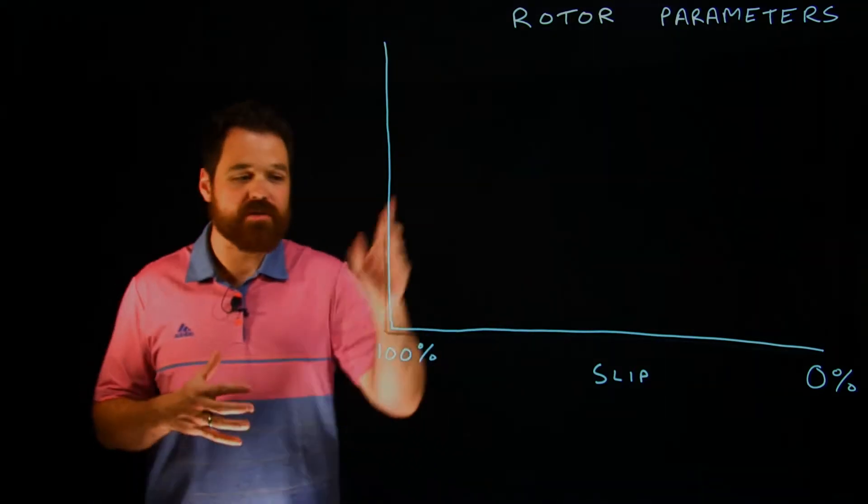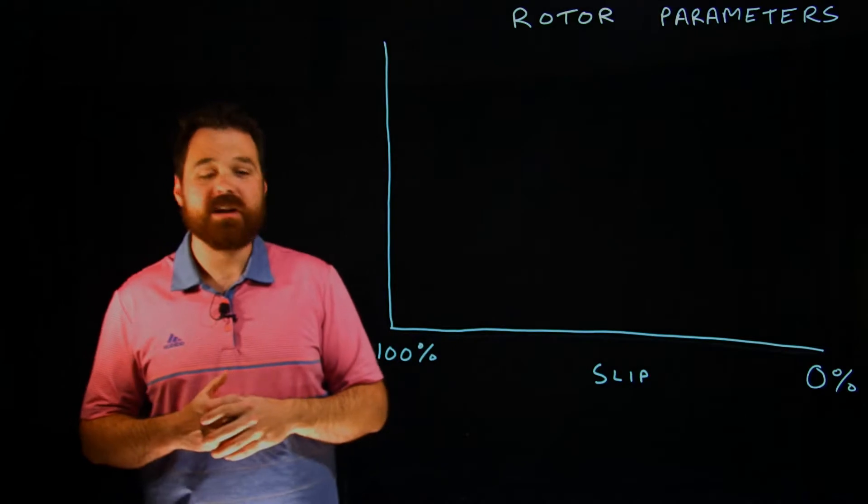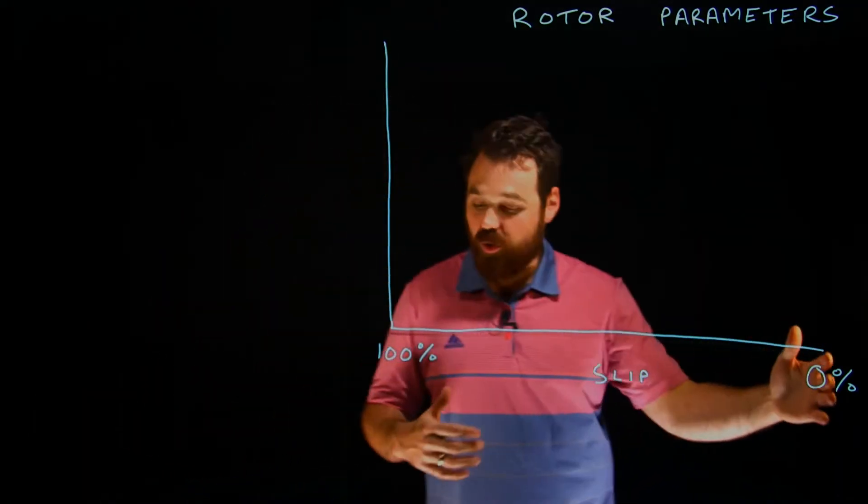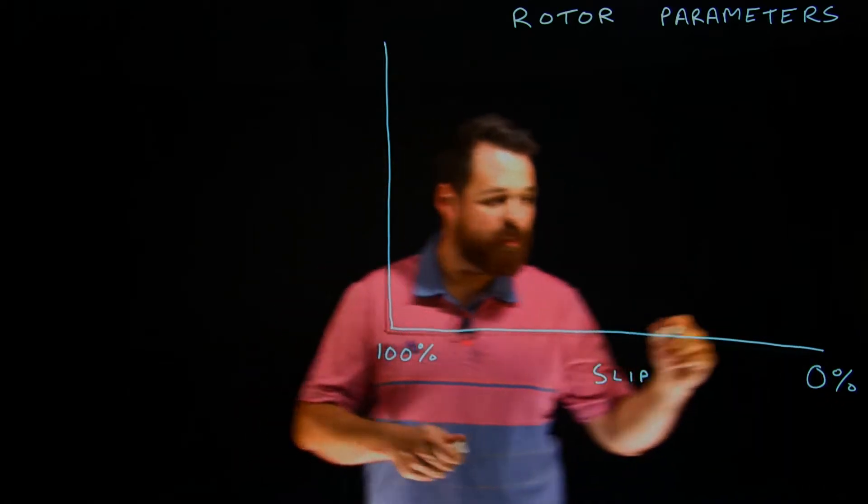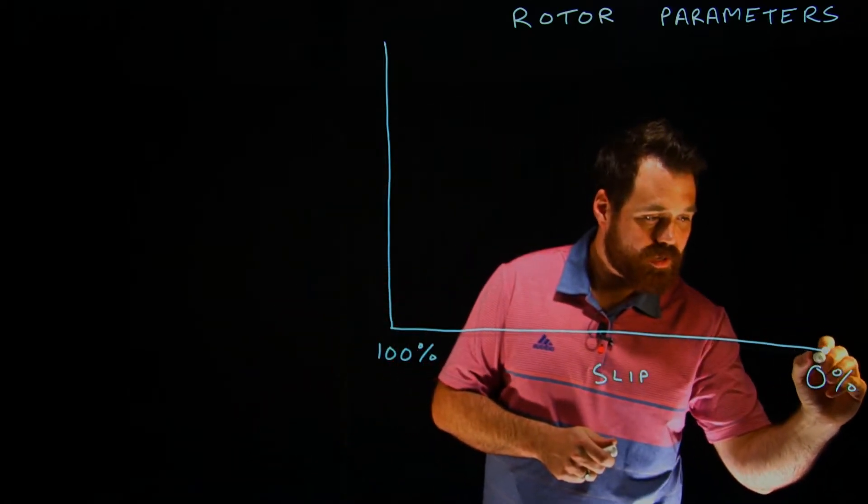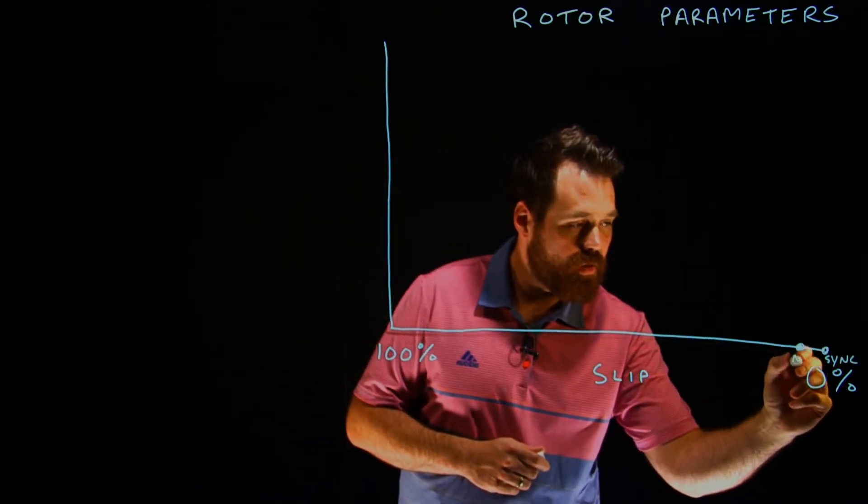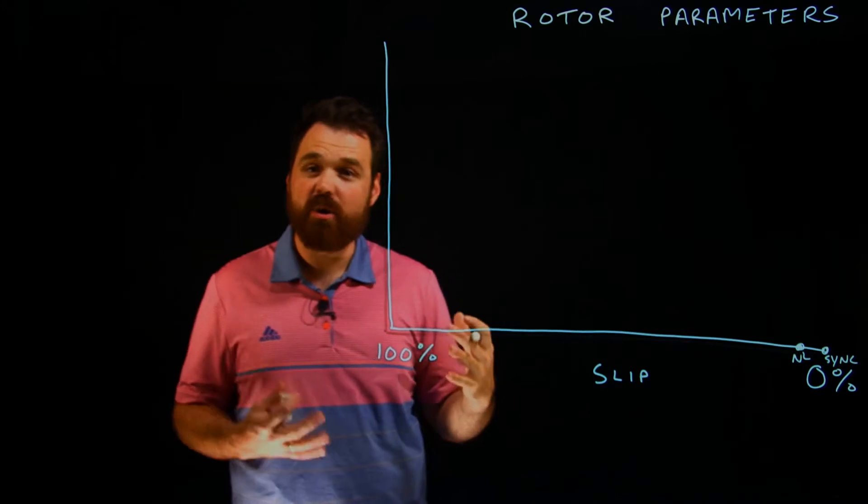So we're just going to draw this graph and talk about a couple different things. What this graph has is slip. So we're talking about our 0% slip would be basically our synchronous speed up there. And then we would have no load speed really close, like two to five RPM away from sync.